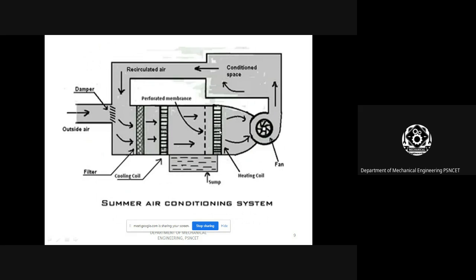The purpose of the heating coil is human comfort. The air is heated, then circulated to the conditioned space by means of this fan. So the cooled air is forced by the fan and circulated to the conditioned space. This conditioned space is fully cooled and dehumidified to the comfort condition. That air extracts heat from the human body, furnitures, and all the things. Again, that heated air is circulated to the system. Once again, it is passed on to the filter, cooling coil, dehumidifying membrane, and then heating coil, and the cycle is completed. This is the summer air conditioning system.